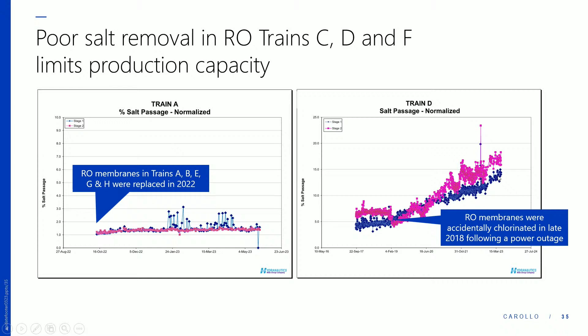This graph over here is from train D, one of the bad performing trains, and you can see that the dates here start in 2017 and go to 2023, but the salt removal starts at roughly 95% and now it's maybe 85%. So it's time for these membranes to be changed if we want to improve the bypass capacity and help with the nameplate production.